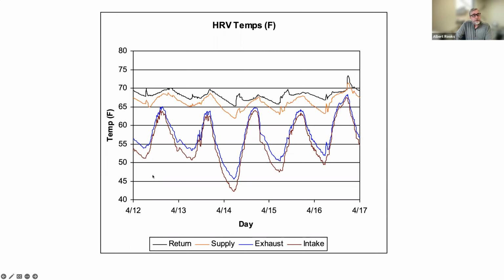And essentially, this is what an HRV looks like in operation. The top line is the exhaust flows coming back from the kitchen and bath. The next line down, that kind of orange line, is the supply flow after the heat exchange in a heating condition. So that's what's showing up into the kitchens and bedrooms. And so that's not very cold. You know, the unit that's being used here is in that 90% effective rate. So the lines below that are the outdoor conditions.